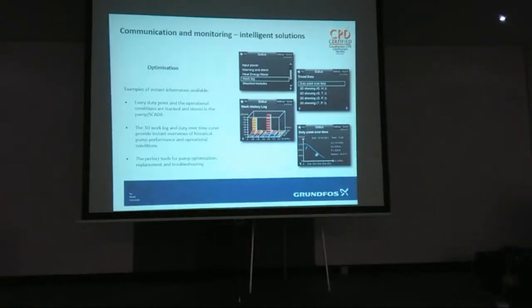And there's the information on the screen to prove the probable demands on booster systems, for example. It used to be a booster set that big. Then it was BS 6700, it's that big. Now it's EN 806, it's that big. But everything's come down and down and down. Less water's used all the time, and the heat emitters got better.